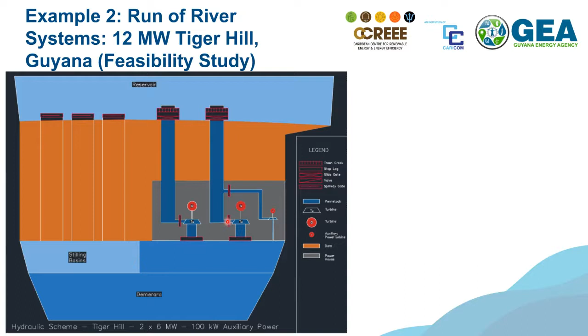If you want to have a black start, you need some primary energy to get going. So that's a little excursion into hydraulic schemes. Auxiliary power, maybe 50 to 100 kilowatts, you can take out and use for self-consumption, for example to open this valve. If you have a blackout, the power plant cannot start without energy from outside, so you can use the small turbine. You can open it by hand, so you have energy at least for the electrical system and to open the main gate and this gate.